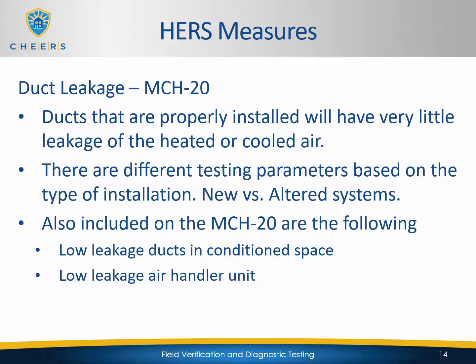duct leakage. So you have your air moves through the HVAC system, it gets heated or cooled, and then it runs through the duct system, which is the distribution system, and it goes to various parts of the house. Well, if those are full of holes and they are under pressure, whether it's the supply ducts under pressure or the return ducts under a negative pressure, well, you don't want to have that heated and cooled air just flowing out into the attic. You want it to go where it needs to go, to the supply register in a specific room. So we really want to keep these tight. There are several different parameters, as we mentioned, new versus altered versus low leakage ducts versus low leakage air handler. So you really have to pay attention to the CF1R documents to ensure that you're testing to those right and correct parameters.